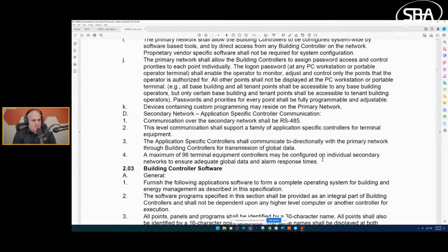All right. You also know that they're doing a big no-no in here. Big no-no. Not good. Maximum 96 TECs on an individual secondary network. I know that you can do it, but just because you can doesn't mean you should. If you've listened to me for any amount of time, and I know I'm preachy, if you follow the RS-485 standard, 64 devices, 32 on each segment, you're not going to get in trouble. As soon as you go above 64, you risk data issues.